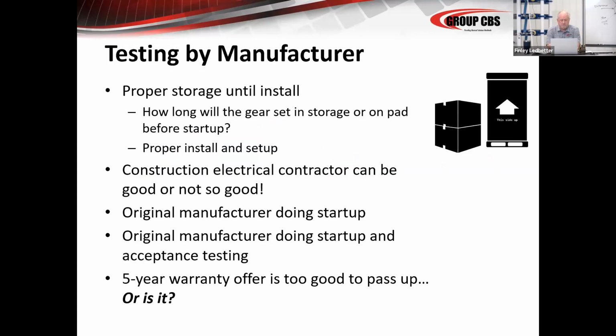So it starts out with proper handling, you know. Probably it starts out with buying the right equipment, but everybody doesn't have the option to be involved in that loop. So when the equipment shows up to the plant, how long does the gear sit in storage or on a pad before startup? Does it sit outside? Does it sit in a climate controlled warehouse? Is there heat on it? Can you run heater circuits to it? Can you keep it warm? Did it get exposed to moisture on the way there?